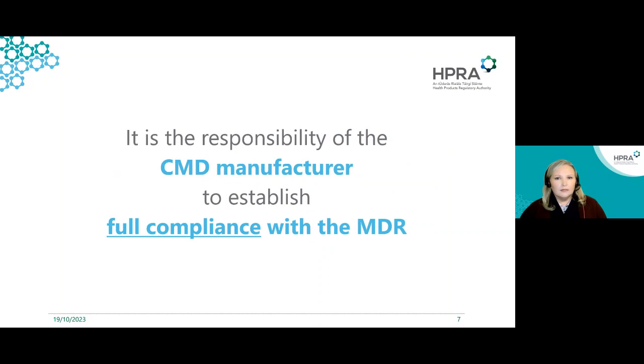Whose responsibility is it to establish and confirm compliance with the MDR? Well, the responsibility lies with the manufacturer. The manufacturer must establish full compliance with the MDR. To do this, every element of the MDR must be reviewed for applicability, and only the specific exclusions and exemptions can be omitted from the approach to compliance.